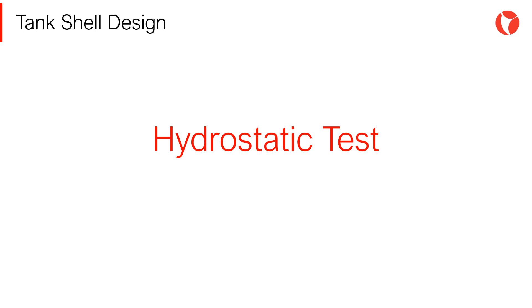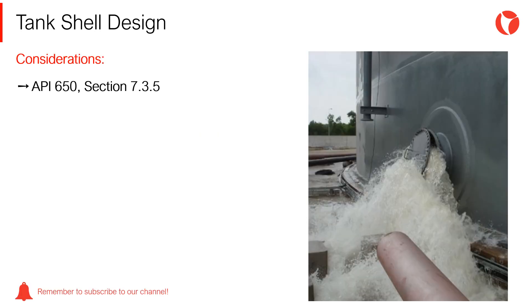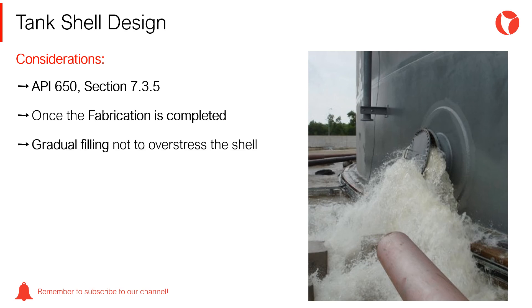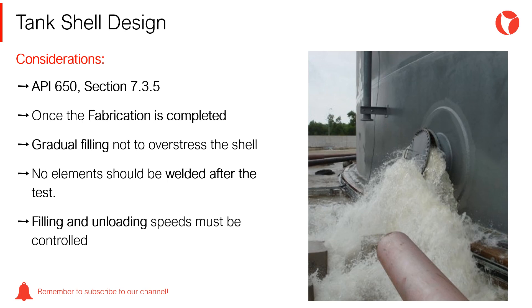The hydrostatic test is carried out to check the tightness of the welded joints. The test is carried out in accordance with section 7.3.5 of the API 650 code. The following considerations must be met: the test is to be performed once the fabrication is completed; the filling must be gradual, not to overstress the shell; no elements should be welded after the test; and the filling and unloading speeds must be controlled. Also, foundation settlements may occur due to the large weights that the tank is transmitting to the foundation.